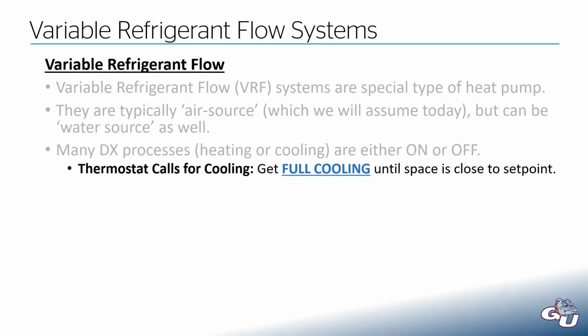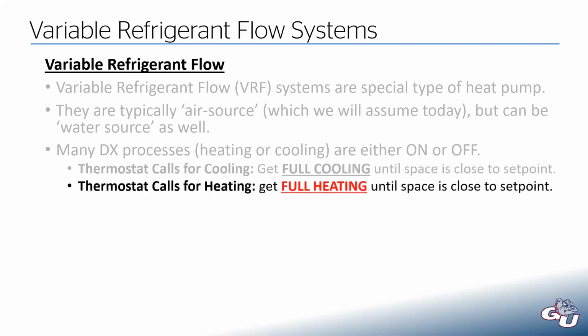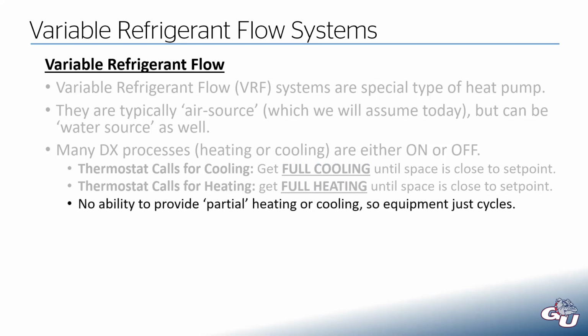It goes to 100% output until the space is happy, gets close to the set point of whatever temperature you want to maintain in that room. And conversely, if your thermostat calls for heating, you just get full heating again until you get to about where you want to be from a temperature perspective. And the issue here is generally you don't have the ability to provide that partial heating or cooling. And the equipment just ends up cycling on and then off and then on and off between 100% output and 0% output.